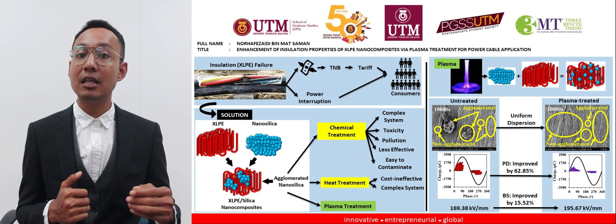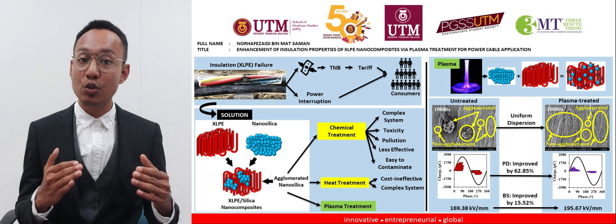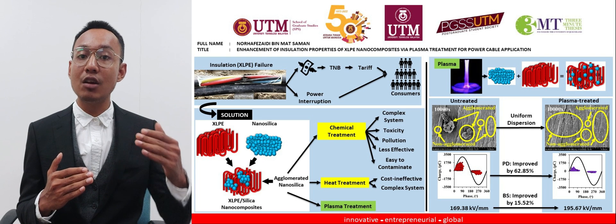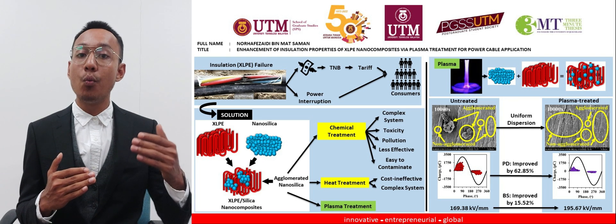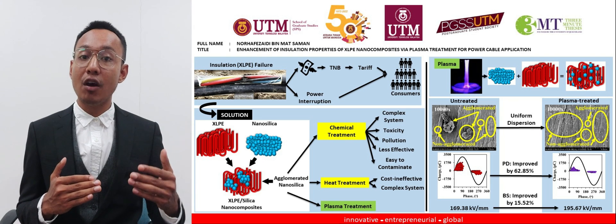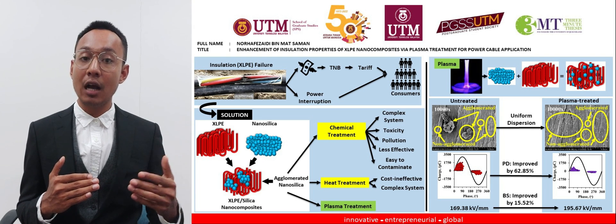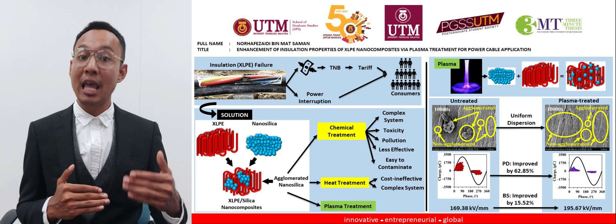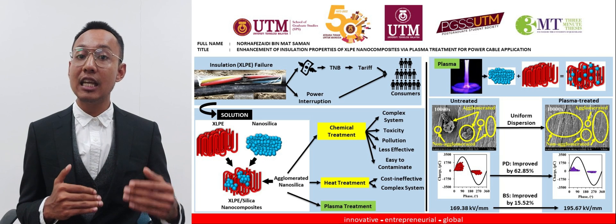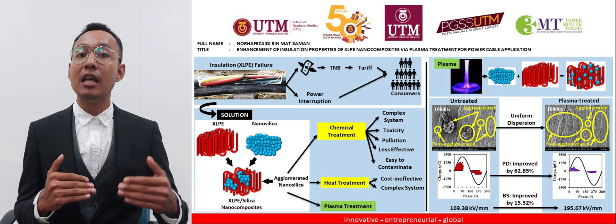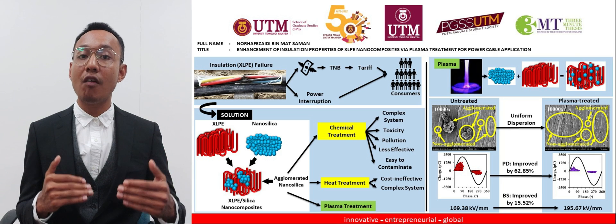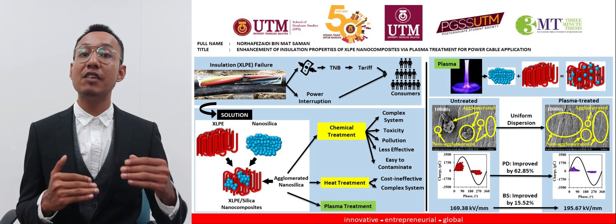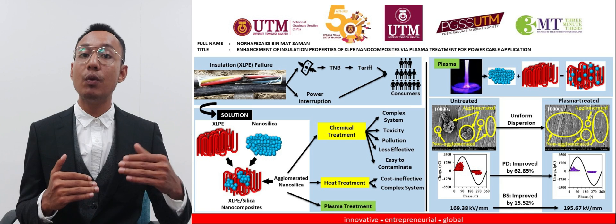Therefore, plasma treatment has been introduced to tackle the issue of agglomeration of nanosilica within XLPE. The dispersion of nanosilica within XLPE was found to be uniform, and it absolutely works to resolve the agglomeration of nanosilica within XLPE by increasing its surface compatibility with XLPE.